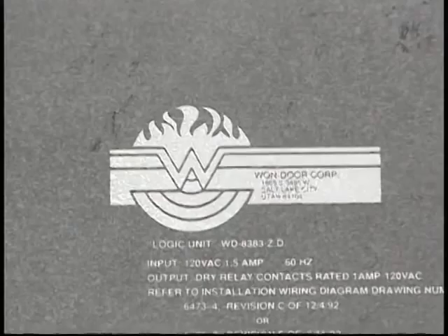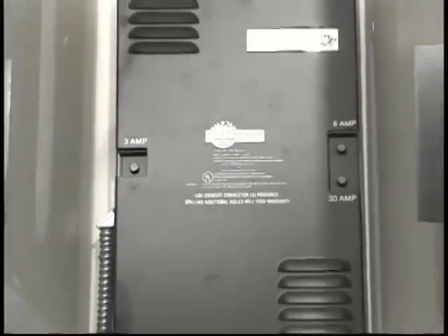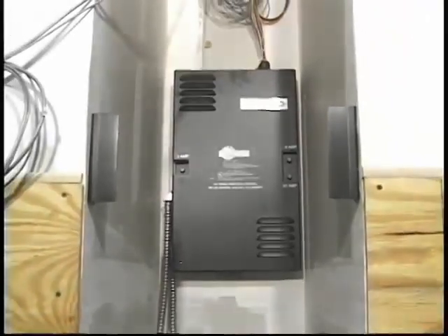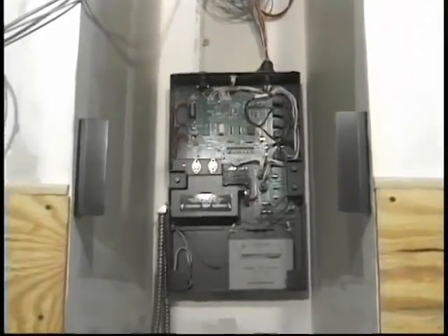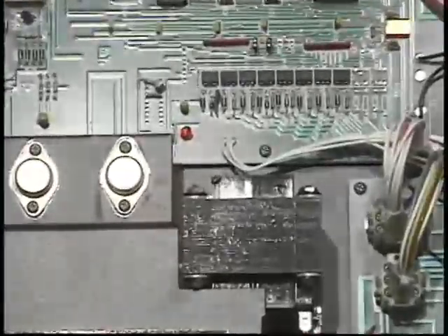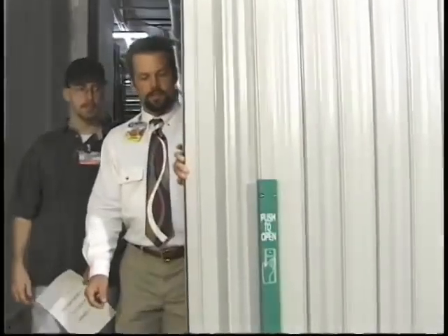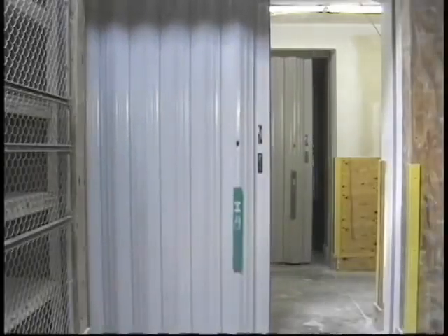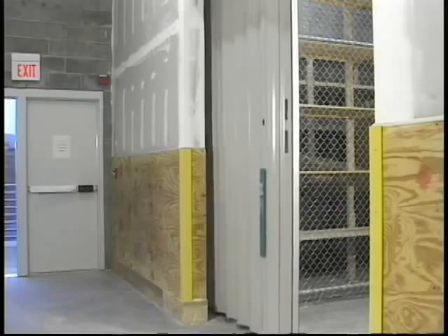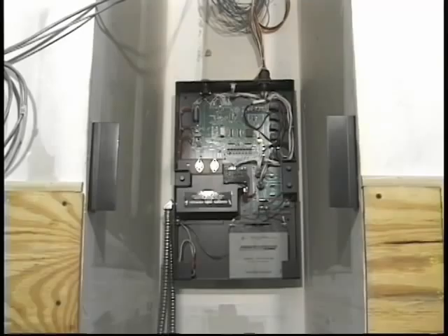The Won Door FireGuard assembly is a completely electronically supervised system. Audible and visual fault signals can be annunciated at the door location, at a remote location in the building, or even to a station away from the building if desired. Not only are all integral components continuously monitored, but the integration of the microprocessor enables the door to actually monitor the opening to ensure that it is free from obstructions.